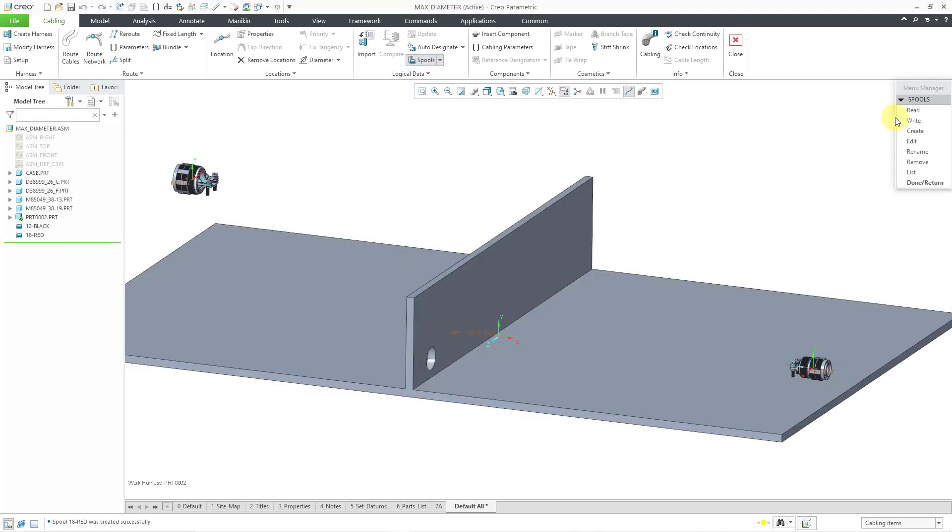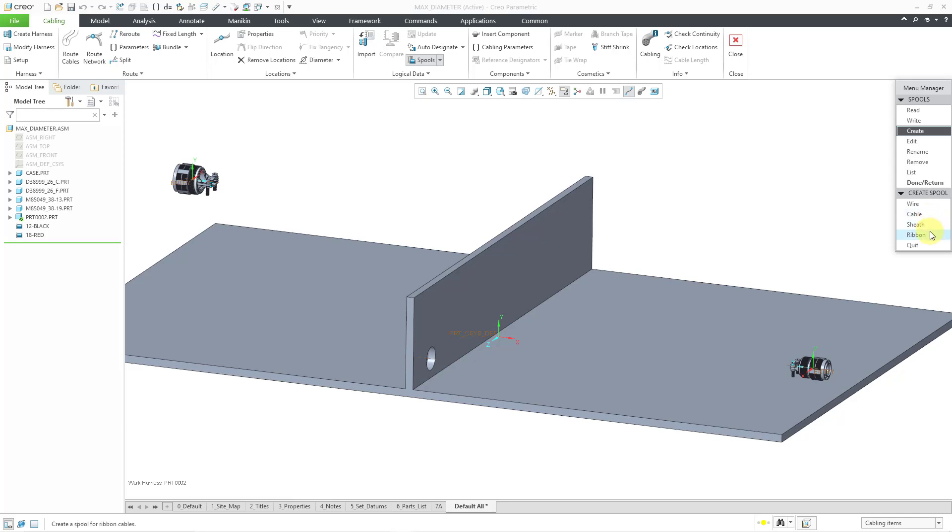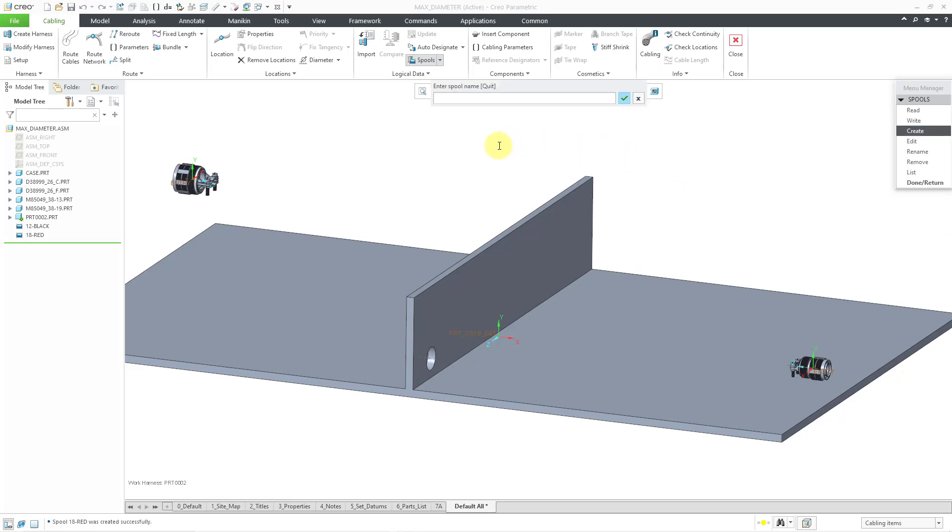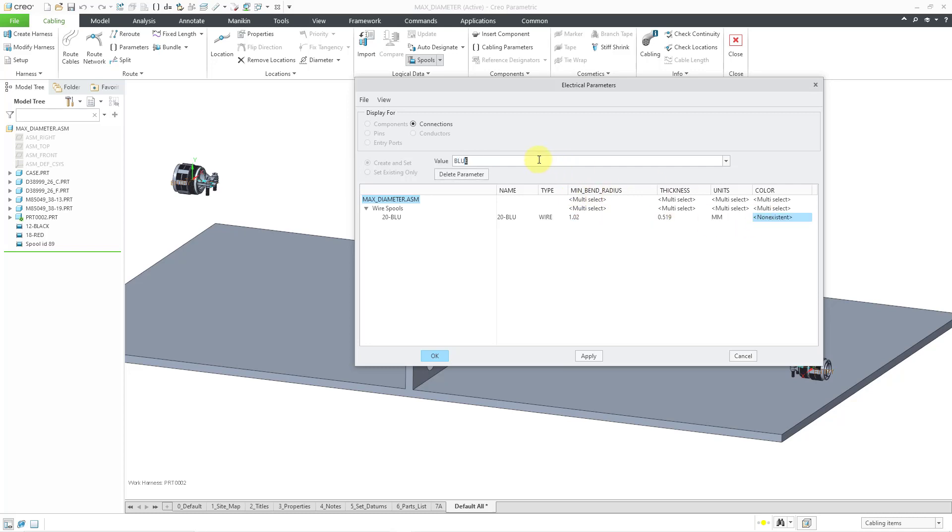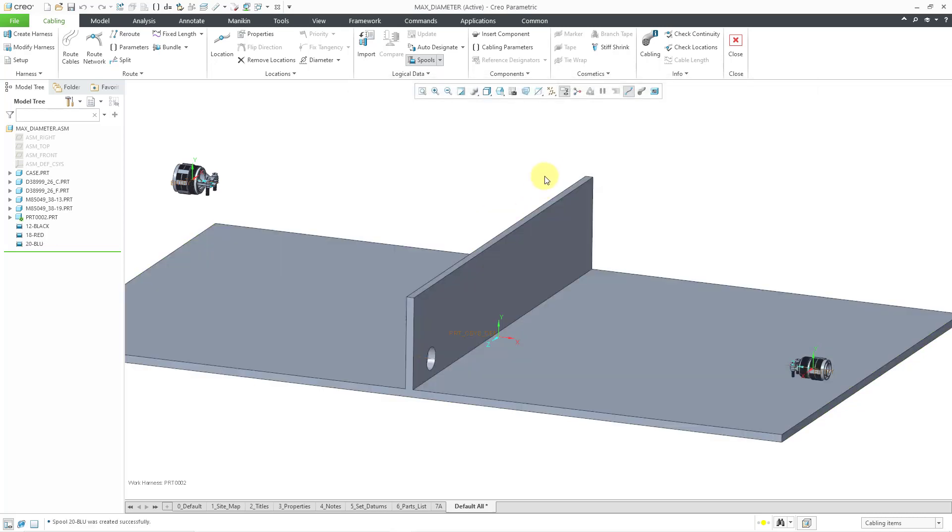And just one more. Let's create a new one for wire. And by the way, you can also see that you can define cables with multiple different conductors. You can also define ribbons like you have for a lot of printer cables, and also sheathing. But let's just choose the wire option. And let's make a 20 gauge blue. And for this one, let's see. For the thickness, that would be 0.519. And for the minimum bend radius, let me use 1.02. For the color, I will use my three-letter code BLU. And then click the OK button. And so now I have my spools created.